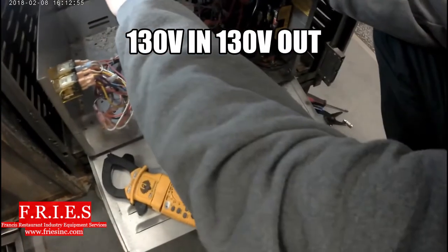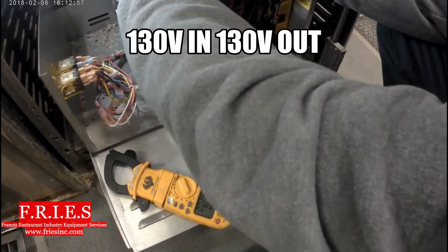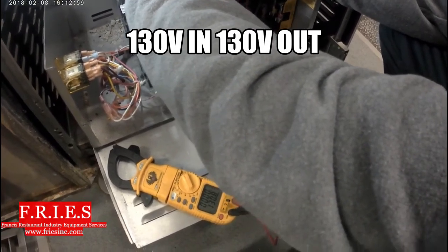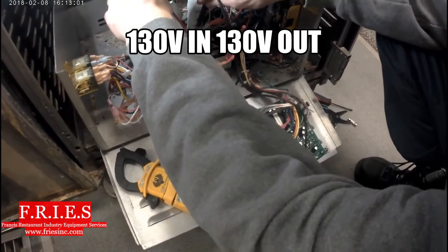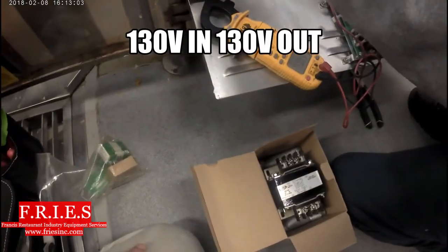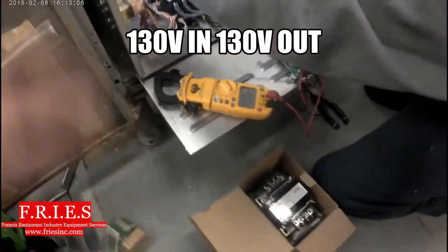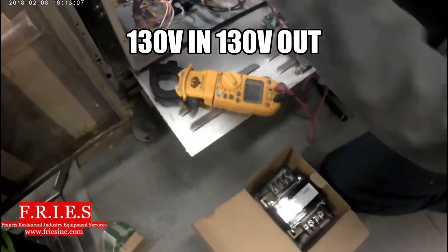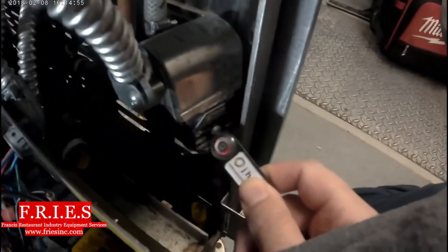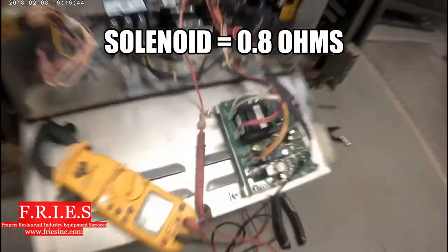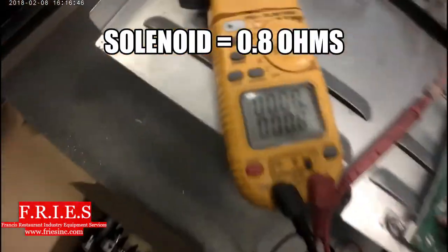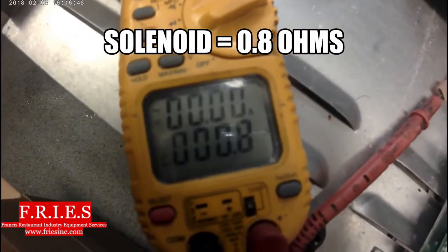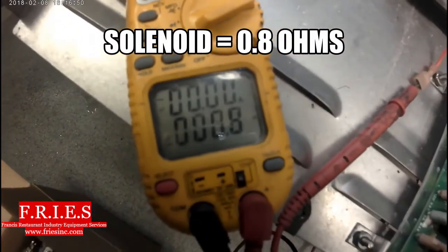All right, so right now I have the drain valve disconnected. I have 130 into my fuses, 130 volts out of my fuses. The unit's running for more than two seconds, which is a huge improvement. And you can see my solenoid, fill solenoid is running—we have power there. All right, then I ohmed out my drain valve. I'm getting 0.8 ohms on it. I disconnected both wires from it.